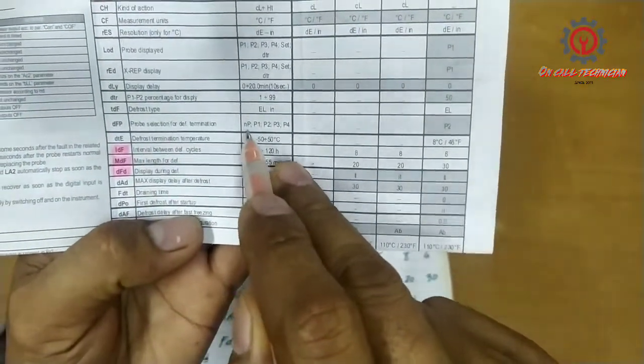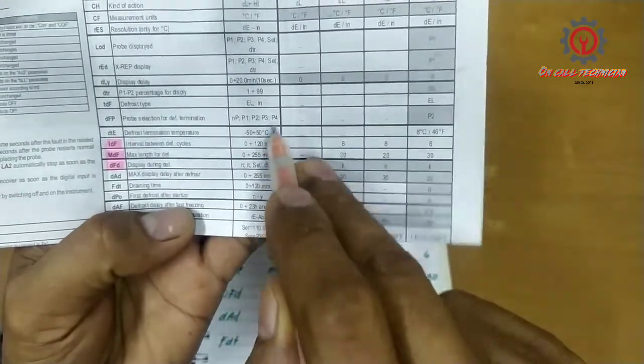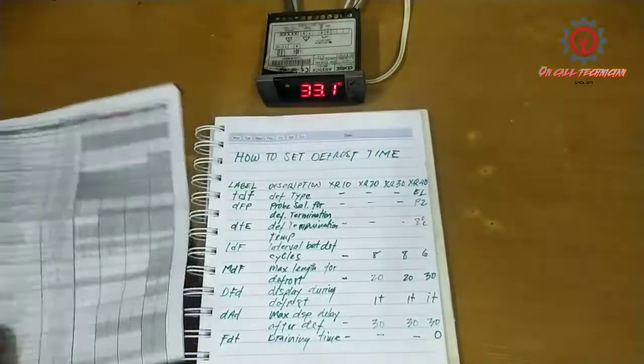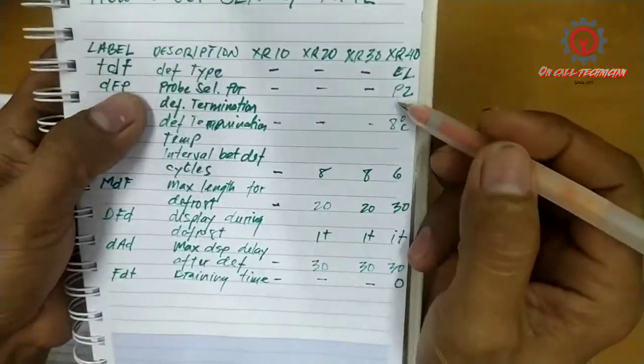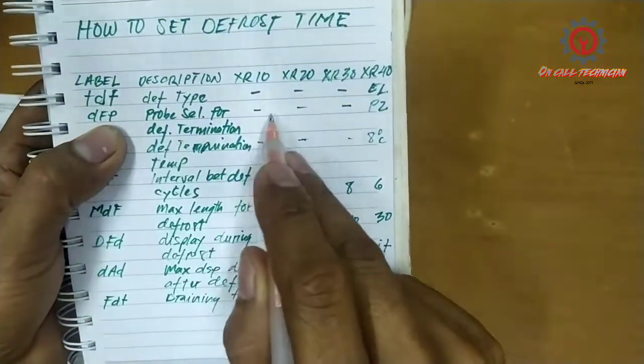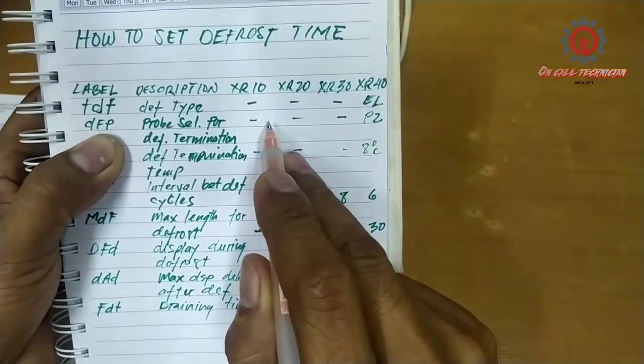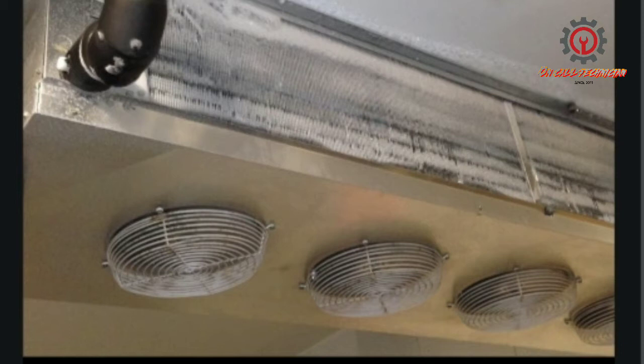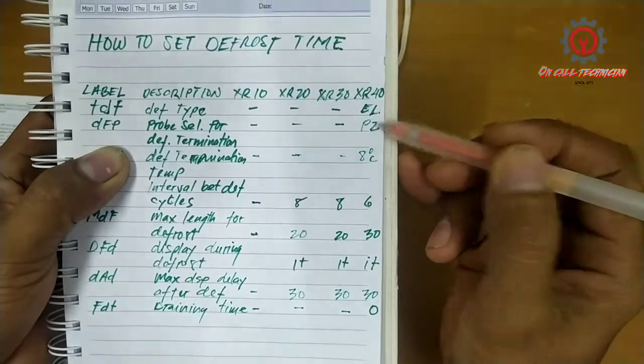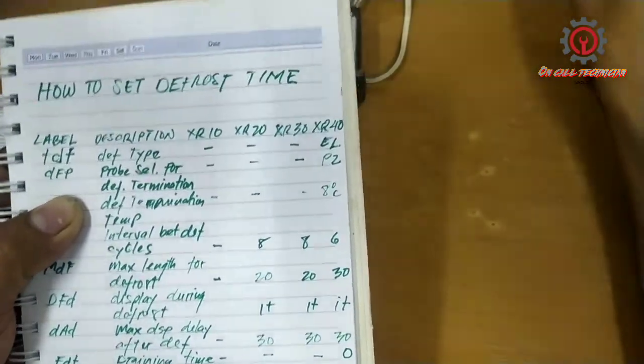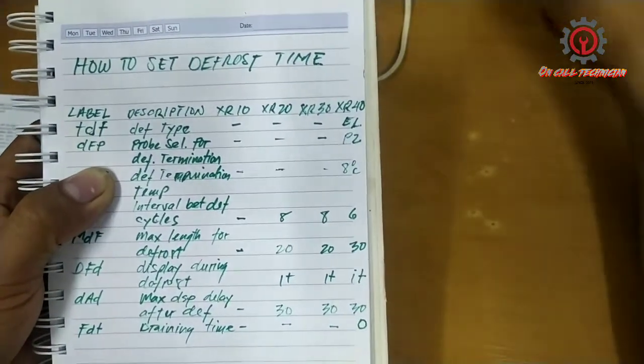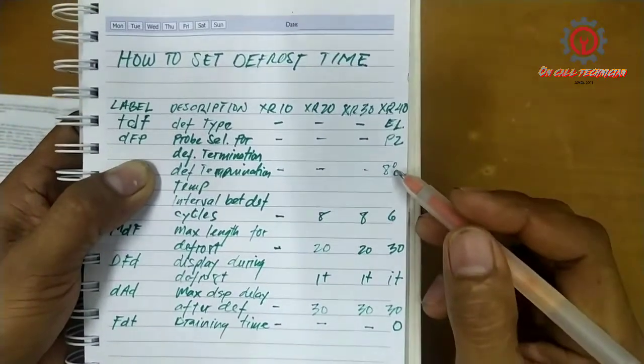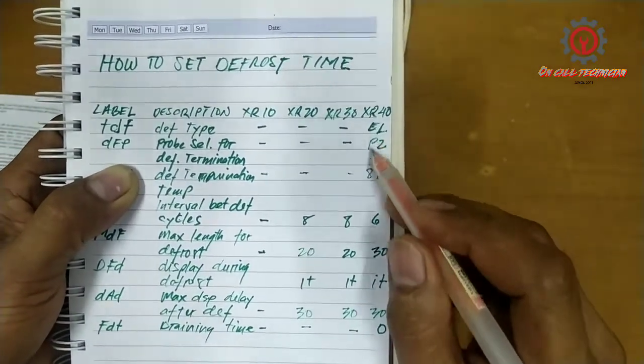makakapamili tayo dyan guys. Under ng DFP, meron itong selection na no probe, P1, P2, P3, hanggang P4. But default is P2. And in this case guys, in the other models of Dixell, I'm not recommending to disable the probe 2 sensor, because probe 2 is intended for the evaporator sensor, and it senses frost accumulated on the evaporator. That's why it's not recommended to disable this one. But if you're going to use 2 probes of any brand of Dixell, you use that in a freezer, use the probe 2. If you use that in a chiller, you can disable the probe 2. Okay?